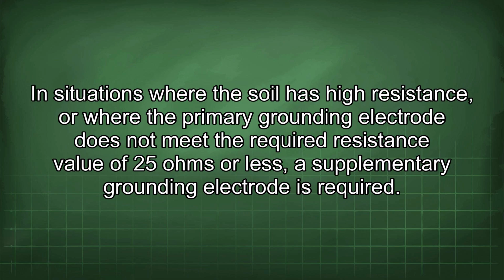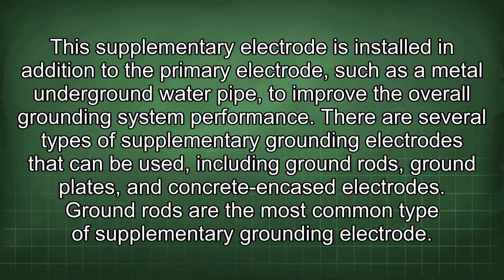In situations where the soil has high resistance, or where the primary grounding electrode does not meet the required resistance value of 25 ohms or less, a supplementary grounding electrode is required. This supplementary electrode is installed in addition to the primary electrode, such as a metal underground water pipe, to improve the overall grounding system performance.